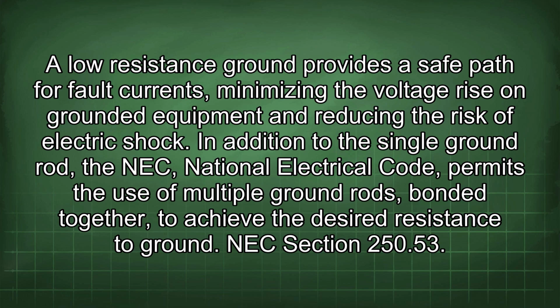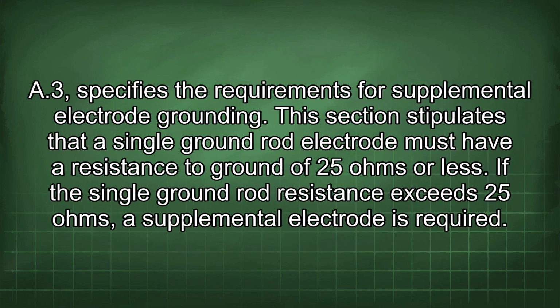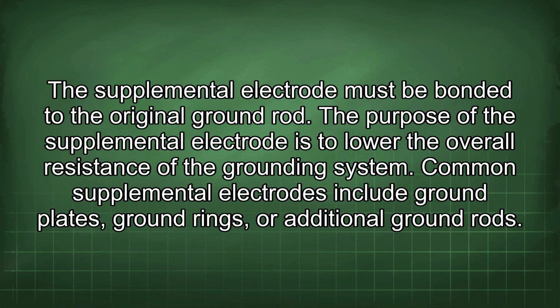NEC Section 250.53(A)(3) specifies the requirements for supplemental electrode grounding. This section stipulates that a single ground rod electrode must have a resistance to ground of 25 ohms or less. If the single ground rod resistance exceeds 25 ohms, a supplemental electrode is required. The supplemental electrode must be bonded to the original ground rod. The purpose of the supplemental electrode is to lower the overall resistance of the grounding system.